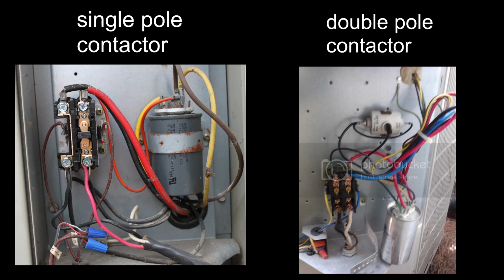If you notice on each side, you see a brown wire connecting on the left side. You'll see another brown wire feeding over to the right side of this one. And that is your 24 volts that's feeding in from the indoor unit. That's that common, the common and cool, which is your Y. Those two that are connected run outside and then feed to the wires. Now you see the little blue wire nuts? The red and white are connected to the brown, and it feeds to the contactor. And that's where it makes its splice.